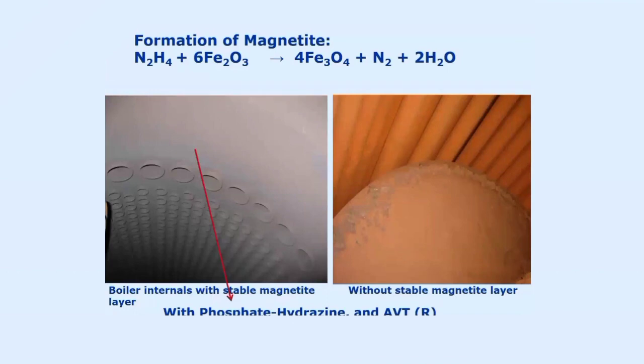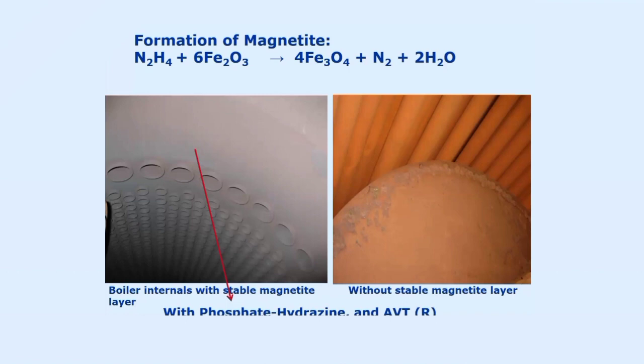So how and when is the magnetite formed? When we are using the treatment of phosphate hydrazine, which is a conventional treatment, or the all-volatile treatment — AVT stands for all-volatile treatment and AVT(R) stands for all-volatile treatment reducing — under such conditions, we develop the magnetite protective oxide in our system.